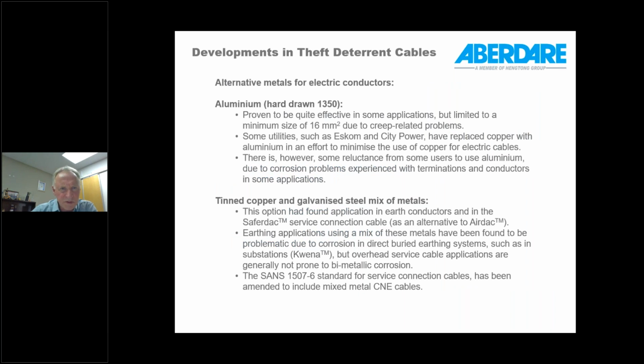So alternative metals can be used for electrical conductors. Obviously, we all know aluminium, hard-drawn 1350. It's a basic aluminium alloy 1350, which we use for stranded conductors in the low voltage and medium voltage space. A number of utilities have actually moved over or started moving over to using aluminium, and we've seen that particularly independent power producers from overseas have really made use of aluminium cables for wind farms and solar PV farms to quite a great extent.